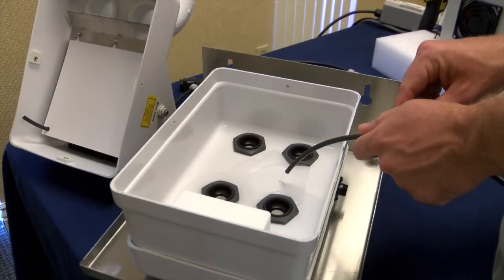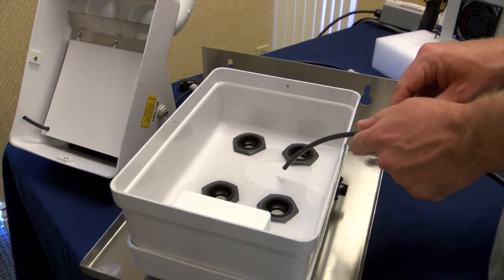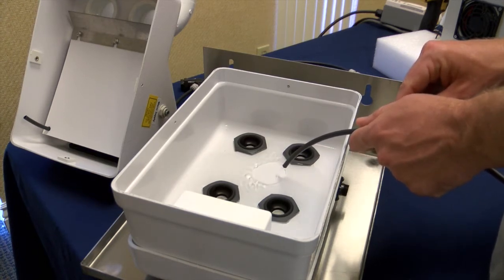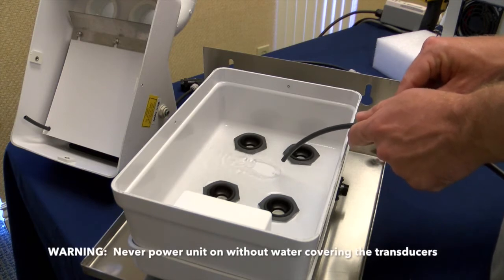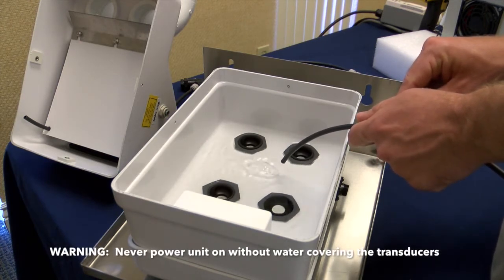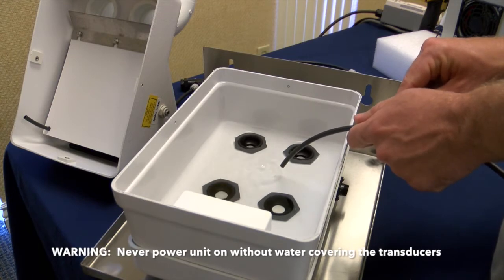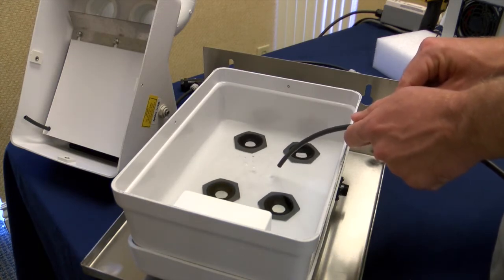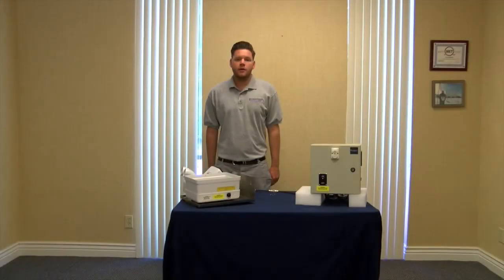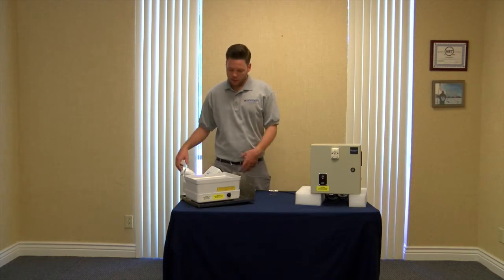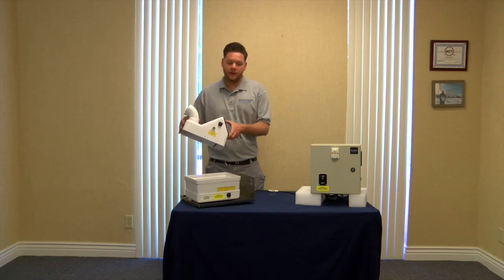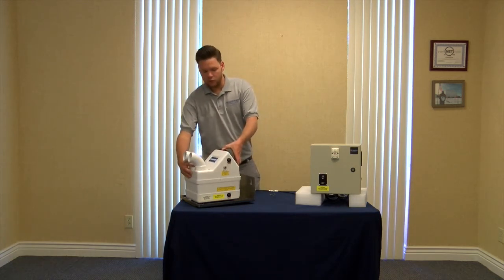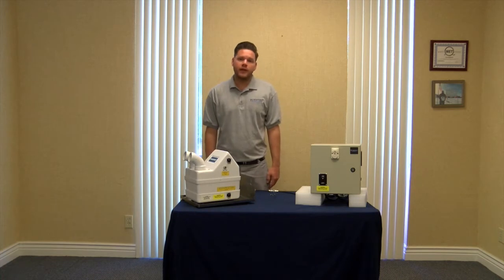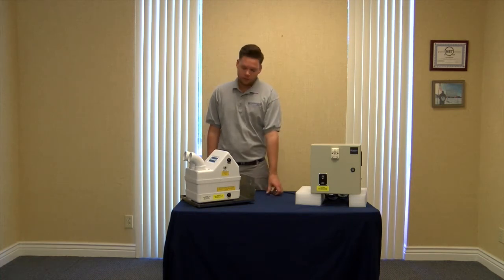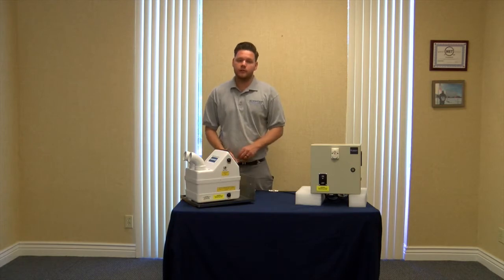You want to add enough water to cover all 4 of the transducers. After you have filled the water pan up with water to cover all of the transducers, you then want to take the top of the humidifier and place it onto the humidifier's water pan. After you have done that, you want to make sure to replace the screws around the humidifier to secure it.